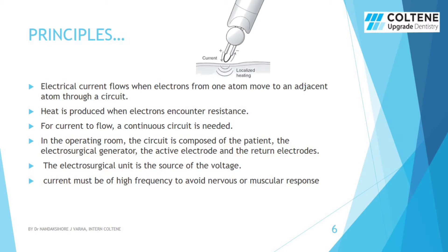Let's see the principles of electrosurgery. Electrical current flows when electrons from one atom move to an adjacent atom through a circuit. Heat is produced when electrons encounter resistance. For current to flow, a continuous circuit is needed. In the operating room, the circuit is composed of the patient, the electrosurgical generator, the active electrode, and the return electrodes. The electrosurgical unit is the source of voltage, and current must be of high frequency to avoid nervous or muscular responses.